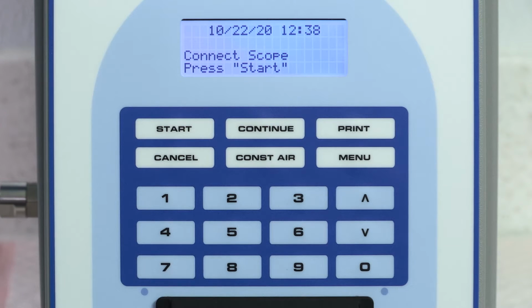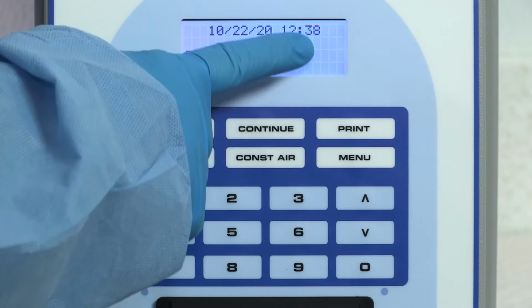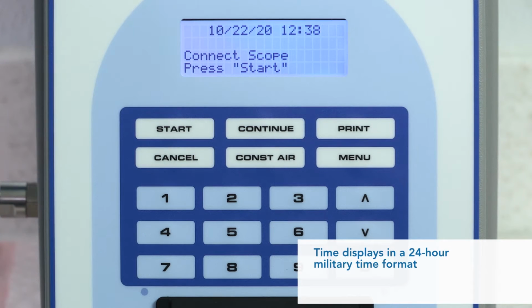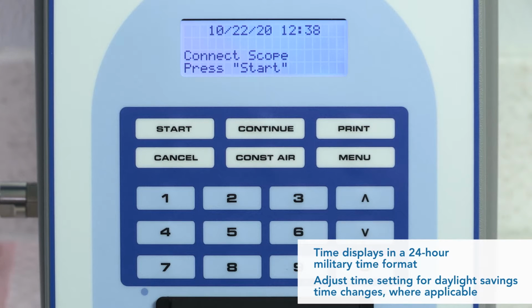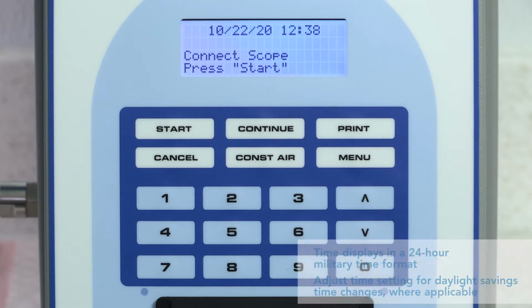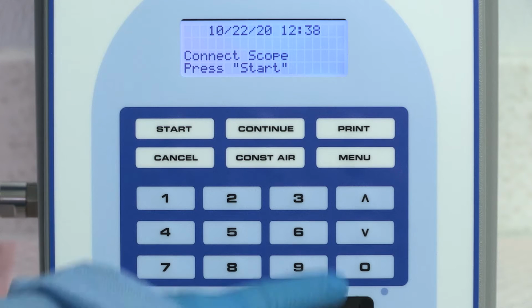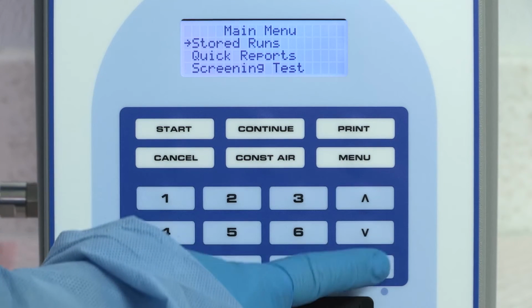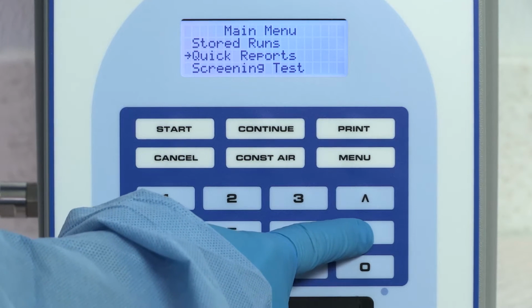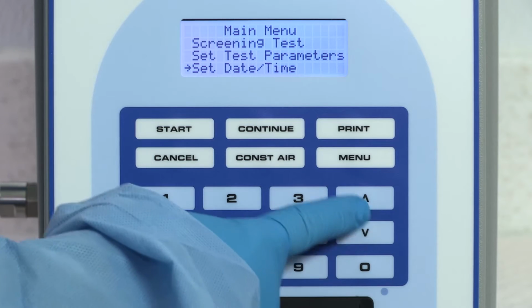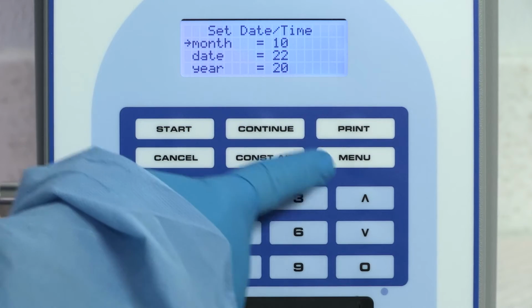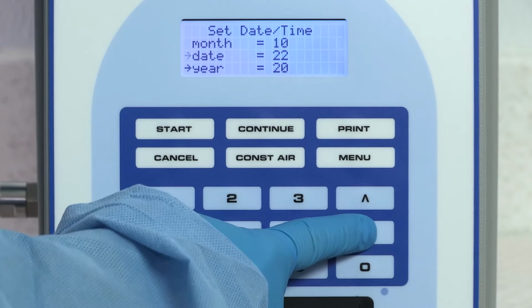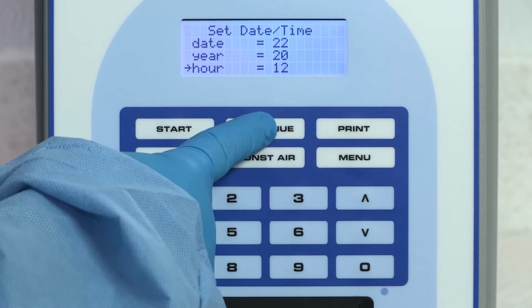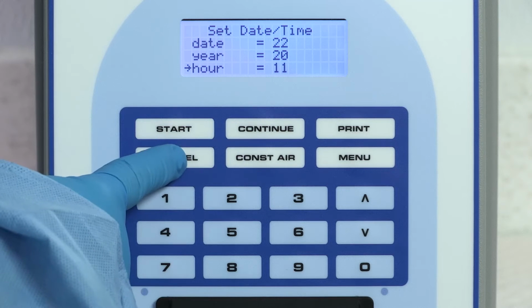First, verify if the displayed date and time settings are correct. The VERISCAN Leak Tester displays time in a 24-hour military time format. The time setting needs to be adjusted for daylight savings time changes where applicable. If the date and time need to be set or adjusted, start by pressing the Menu button on the touchpad. Using the arrow keys, scroll to the Set Date and Time option. Press Continue and use the appropriate buttons on the numeric touchpad to enter the correct date and time information. When finished, press the Cancel button to return to the main screen.